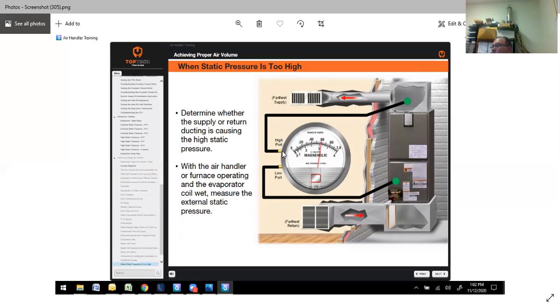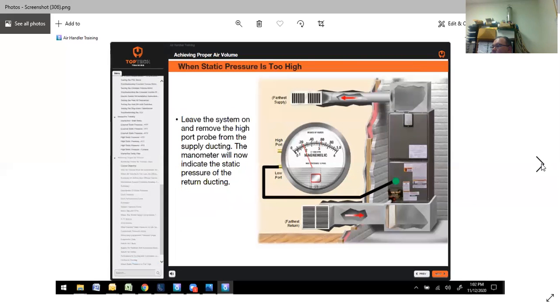So what you want to do, with the air handler or furnace working, they're showing the Magnehelic, but you can use a dual port manometer. Put one in our pre-drilled supply and one right here in the coil, so you're actually measuring both of them. Leave the system on at this point. Remove the probe out of the supply. Okay. Now we've dropped down to 0.22.